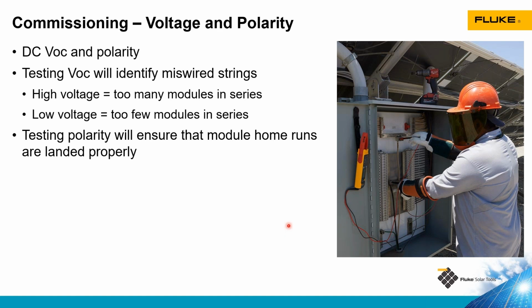If someone were to accidentally wire a positive and negative to the positive fuse holders, if the fuse holder is open, that's an open circuit. Their positive and negative are not connected together. As soon as I close those fuse holders, the positive and negative will be connected through the bus bar, and I'll have a short circuit current flowing through that circuit.